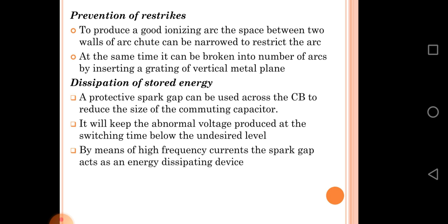Dissipation of stored energy: a protective spark gap can be used across the circuit breaker to reduce the size of the commutating capacitor. It will keep the abnormal voltage produced at switching time below the undesired level by means of high frequency currents. The spark gap acts as an energy dissipating device.